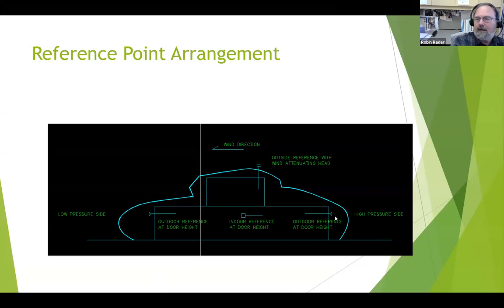And so here is an outdoor reference, and this reference is subject to wind pressure, which can go many times over the control point. Here is another outside reference that is above the building, and it uses a wind attenuating head, which consists of two plates with a little opening in the bottom of the bottom plate. And so then the airflow is orthogonal to this sensing point, and the wind doesn't affect that point. And so you want these things as high as possible. I drew a line here underneath this thing as far as where the pressure envelope goes, but it's hard to tell where that pressure envelope is. So the higher these things are above the roof, the better.